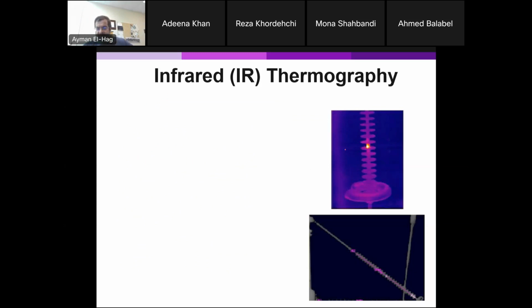So here, this is a non-ceramic insulator, and you can have a localized increase in the temperature. This is most likely an indication of an internal fault. Now, because those insulators, and again, I will mention that in detail next week, have a fiberglass core, and then you have a mold. On top of it, you have the silicone rubber molded on top of the insulator. Sometimes in the mold, there is not good bonding between the rubber and the fiberglass core, okay?